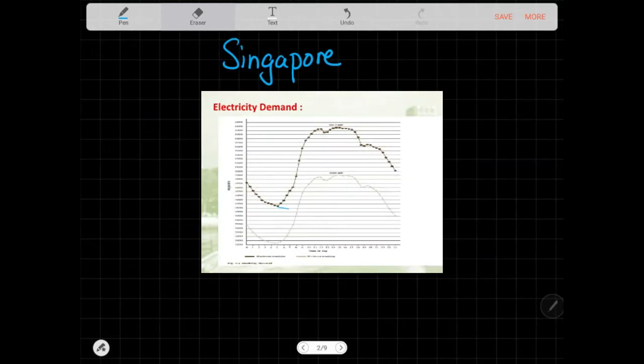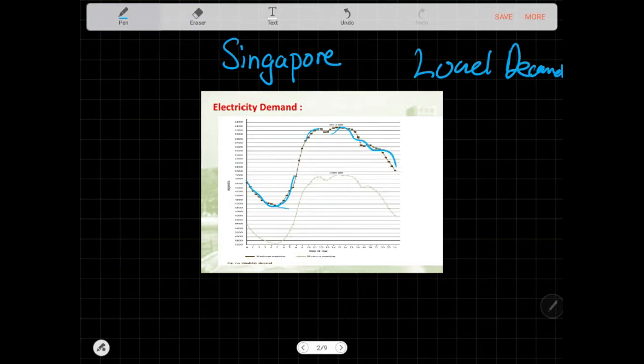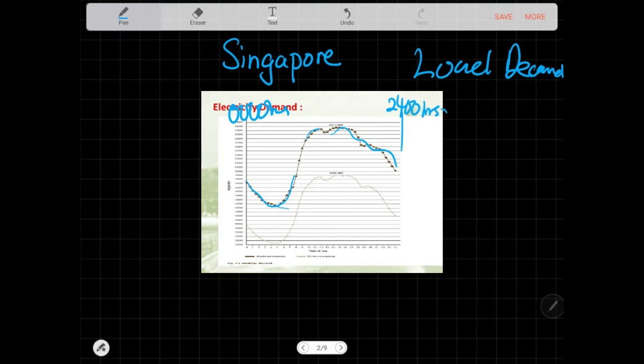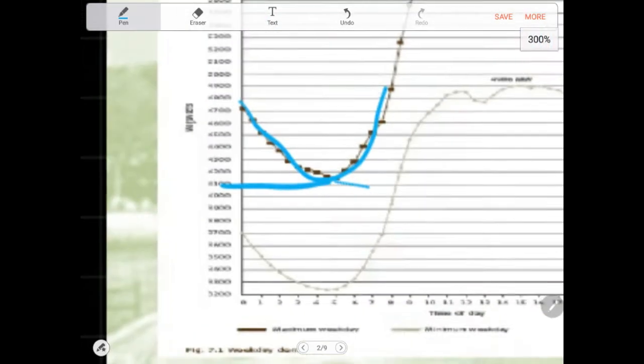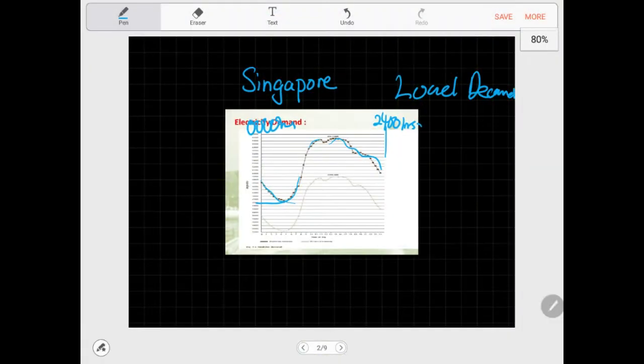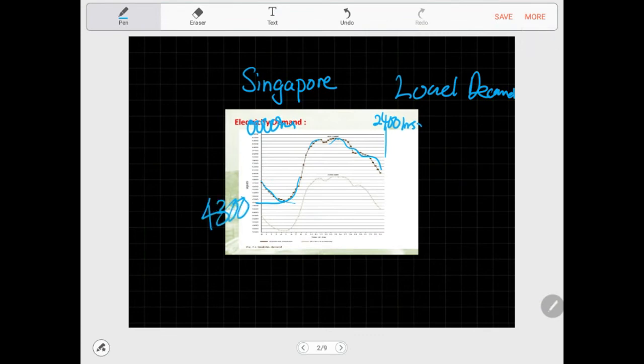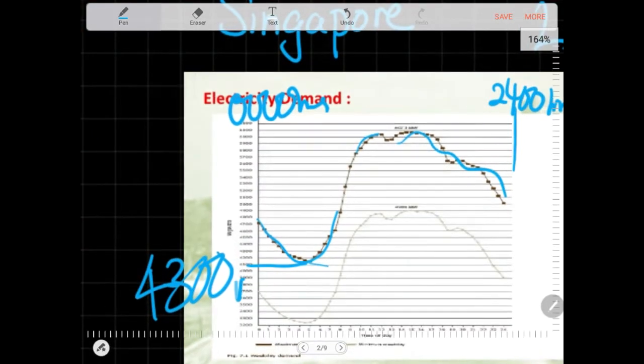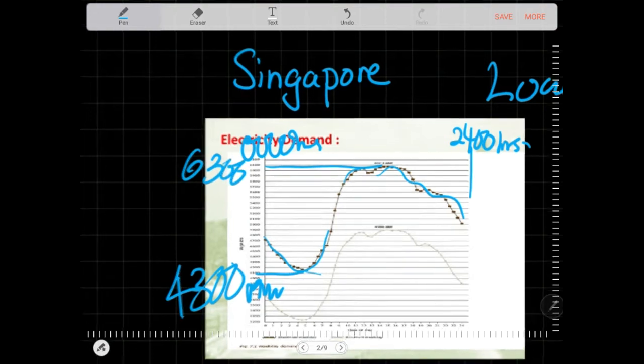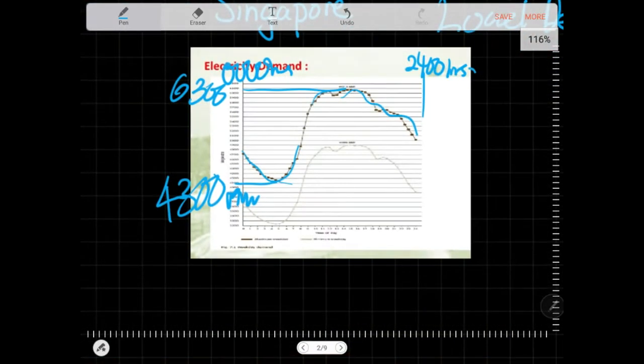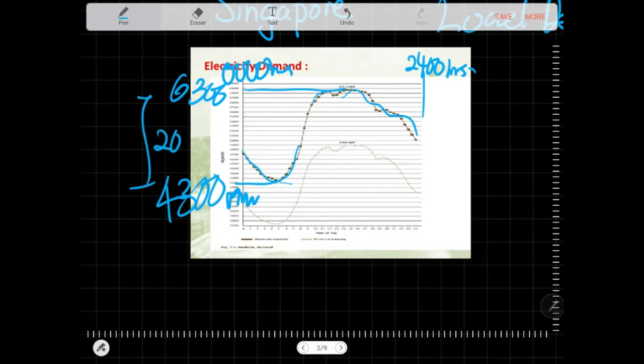In order to understand all this I need to bring in what they call load demand. It's basically from 0000 hours to 2400 hours. What is the demand of electricity inside a country or in an electricity network? What you really need to know about load demand is the maximum and the minimum of the demand. So the minimum of the demand is around 4300 megawatts. This is Singapore load demand. And the maximum in this case is around 6300. It's an expandable range about 2000.